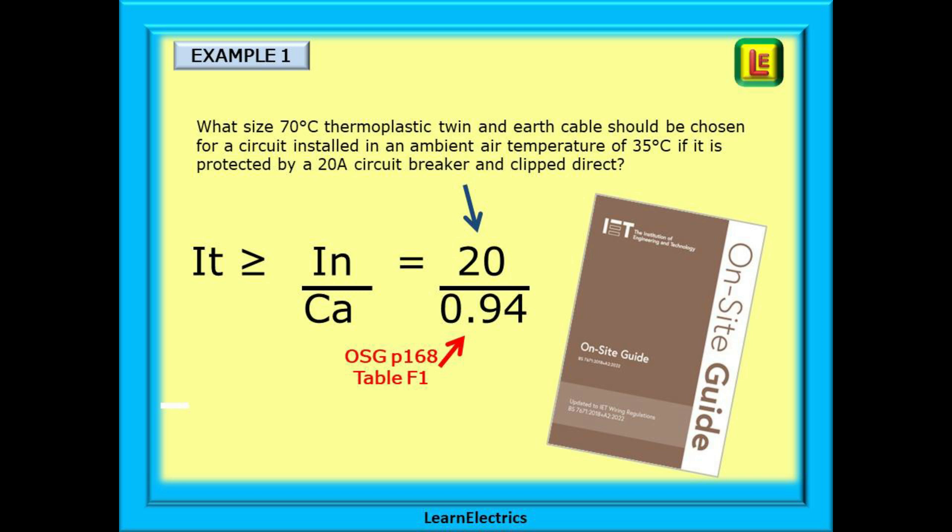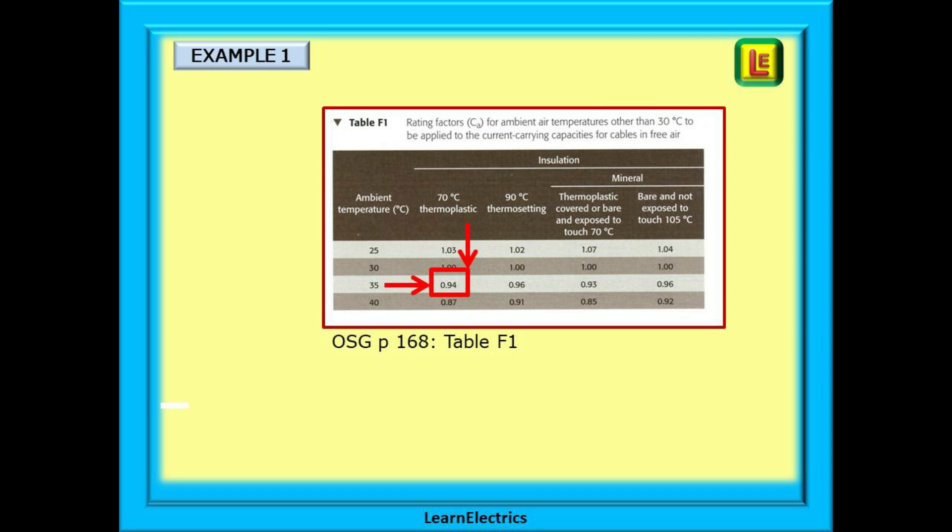So our question and our original formula have been simplified to this. Looking on page 168 of the on-site guide, we will find table F1 that tells us to use a value of 0.94. How have we got this? Find a 70 degree thermoplastic in table F1 as shown here, and follow this down to the row for 35 degrees air temperature, where the two cross is our factor 0.94. Easy.